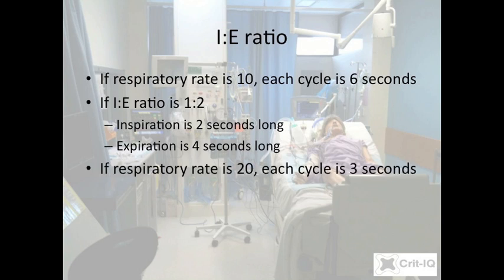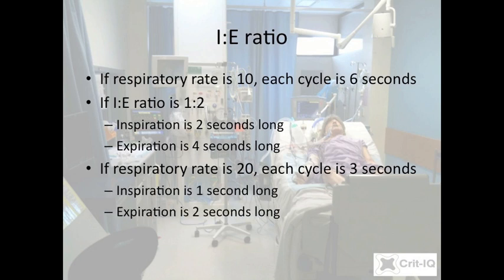If the respiratory rate is increased and the IE ratio remains the same, both the inspiratory time and the expiratory time will be reduced. For example, if the respiratory rate changes to 20, each cycle must now occur in 3 seconds. If the IE ratio remains at 1 to 2, then the inspiratory time will be 1 second and the expiratory time will be 2 seconds. The inspiratory flow will have to double.